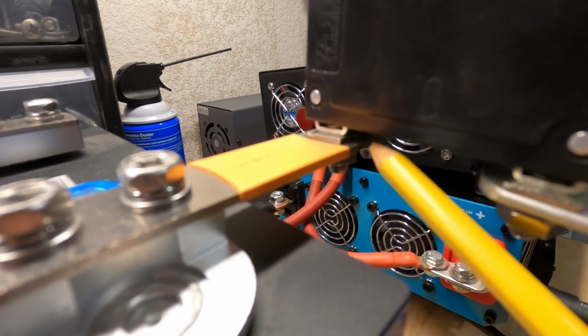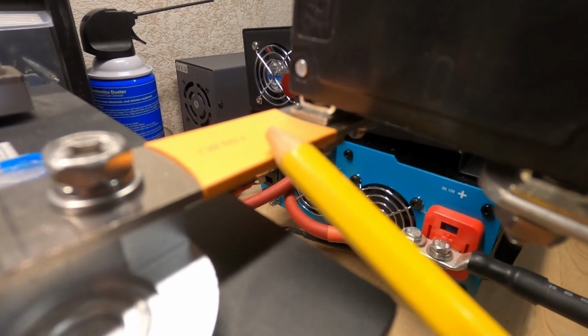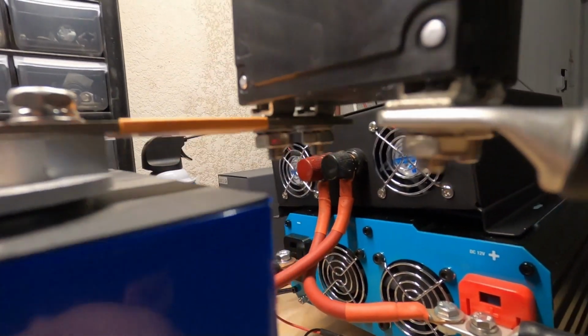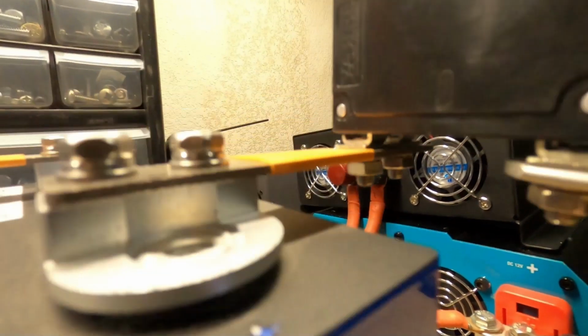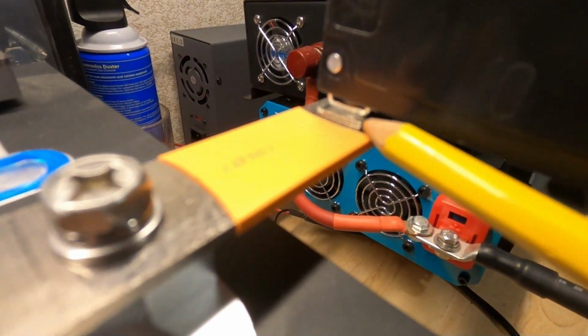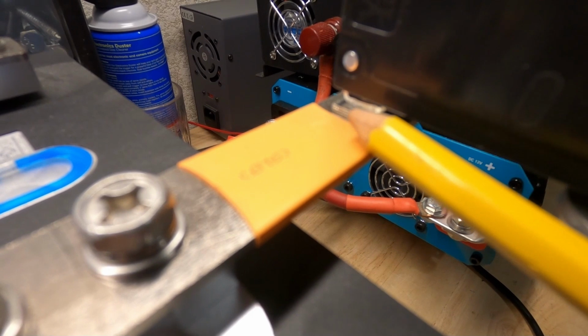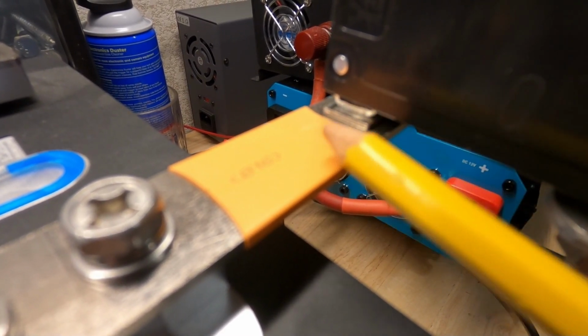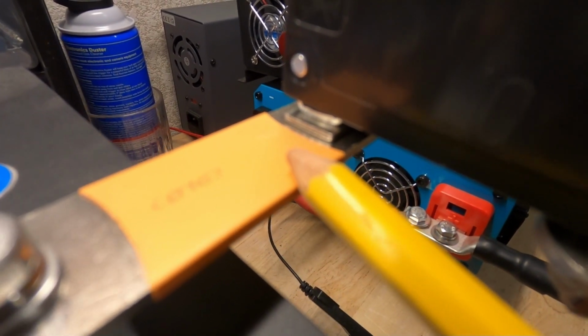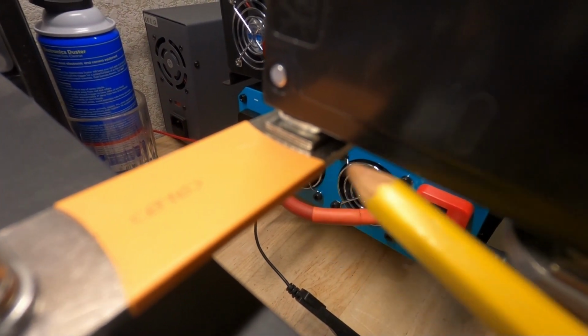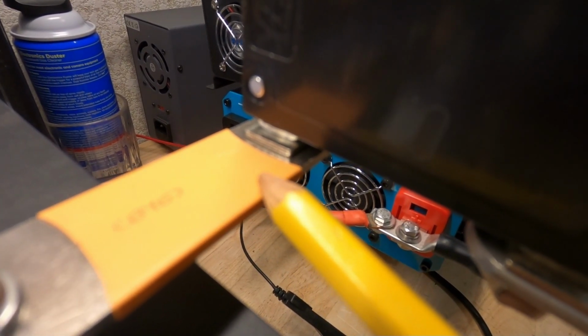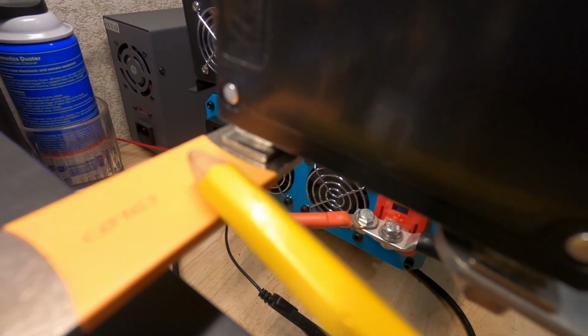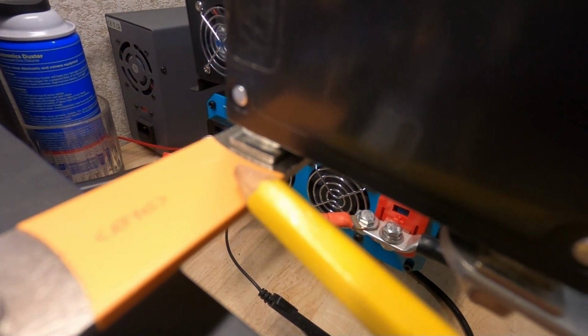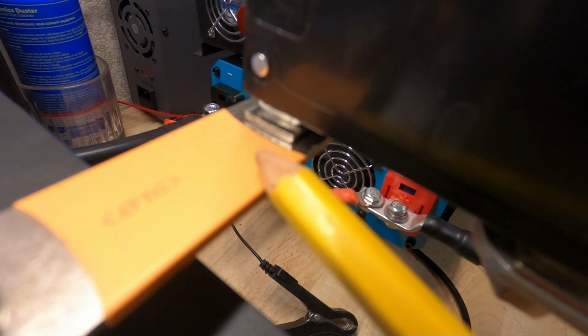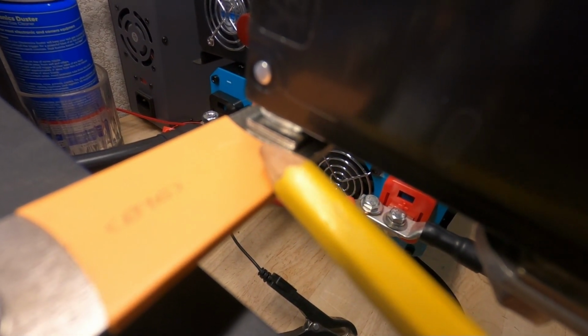Now, it doesn't make sense that they have it on this side because this bus bar has 2 holes on it, so it can span the breaker by itself. So it's very strange that they have this little piece of metal inside there between the contact terminals of the breaker and the actual bus bar. And this is how it is exactly in the box. I have the same setup going on. I didn't want to remove any pieces or parts. I wanted a close simulation of how it behaves in the box. So I'm not quite sure why they have that on this side.